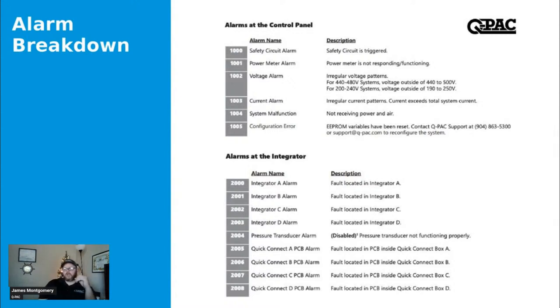What would cause an integrator A alarm? That's just a malfunction or an issue in the wiring. If that device fails, it'll also provide one of these integrator A alarms. So I've got a pretty well-written guide on how to troubleshoot this.